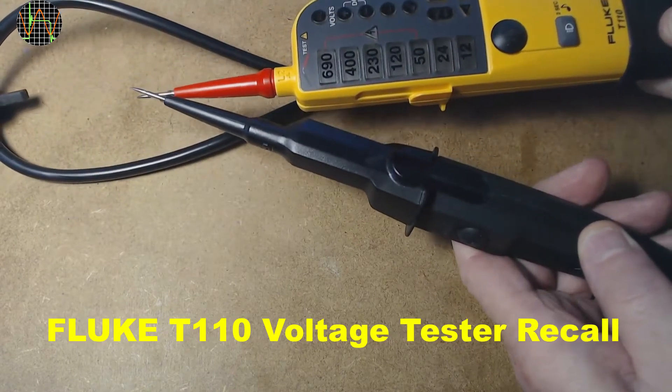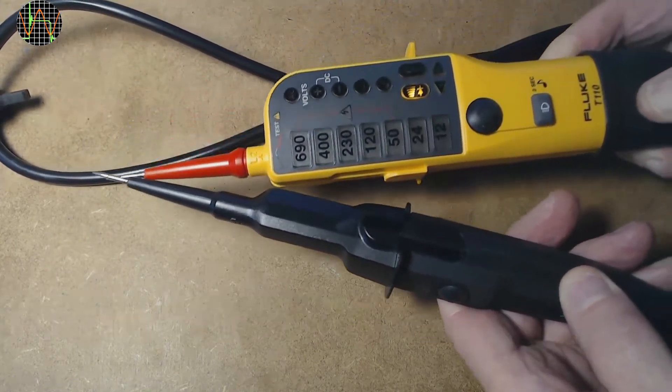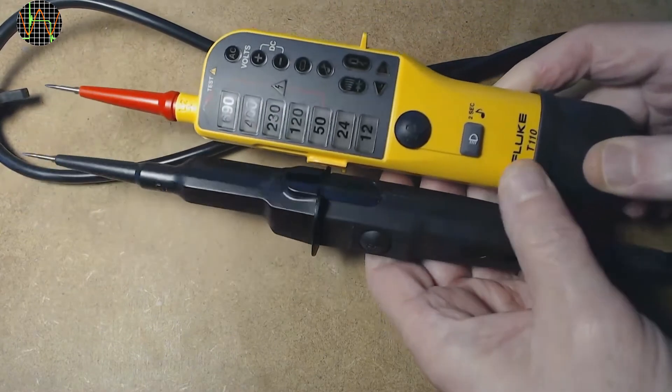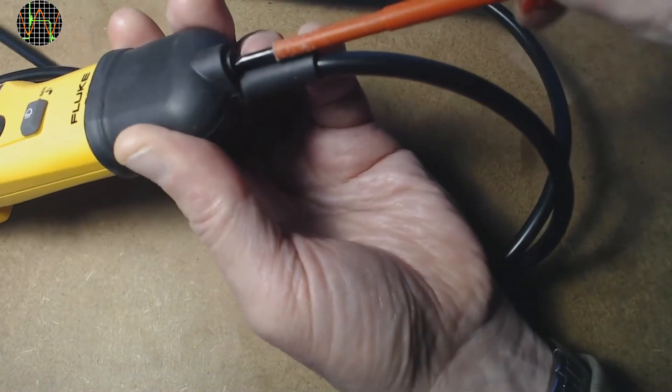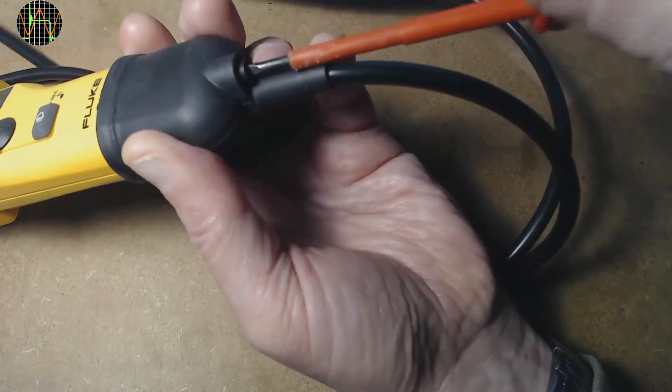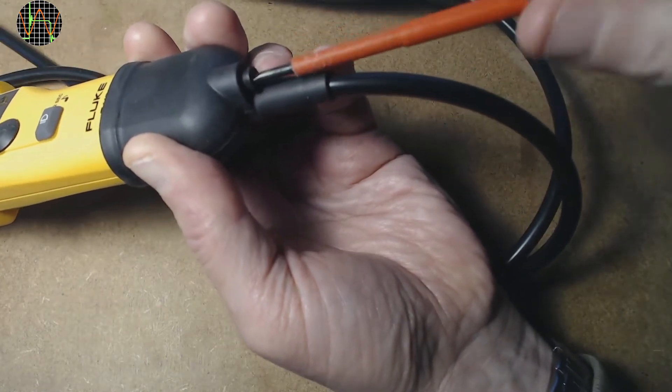Hi there, this is a quick video in case anyone owns one of these voltage testers. I just came across a recall notice sent by Fluke on the T110 and similar tester models asking to immediately stop using them.